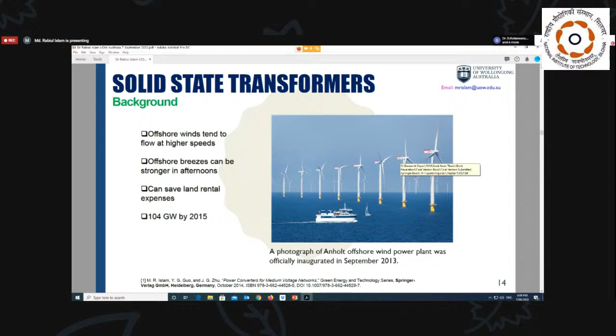First, have a look at what sort of electrical components are inside this nacelle. Here we see this is a traditional system - we can see generator, converter, and step-up transformer. This step-up transformer steps up the voltage from a low voltage level to grid voltage level. Usually we use medium voltage to transfer this power to the main grid. As you see here, this transformer is really very heavy and bulky.